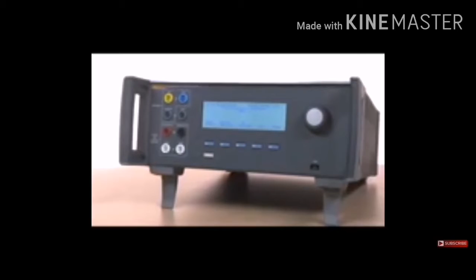Notably, the QA-ES3 has a 20-ohm load to support Valleylab electrosurgical units, including the Force Triad. The QA-ES3 also has double the RMS current range of its predecessor. It can measure current from 0 to 5,500 milliamps. Plus, it's twice as accurate, with current accuracy of 2.5% of reading plus 1 milliamp for all loads. It's exceptionally accurate, with generator output power accuracy of 5% greater than 10 watts and 5% plus 1 watt otherwise.